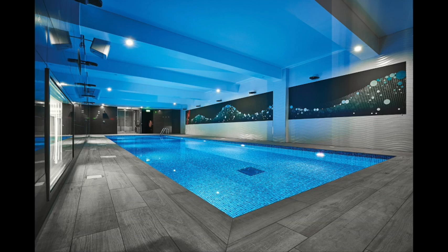Oh, that's interesting. What would you say is the most popular way to heat pool halls? Most pools are heated via ventilation systems. Typically, this would involve supplying air at a temperature of 45. So if it's off a boiler system with water at 80 degrees C or maybe even 70 degrees C, that would not be a problem at all because you'd have a difference of 80 degrees C water temperature to coming back at 45 degrees C, a 35 degree difference. If this was off a heat pump, the water was at 55, which is on the high side for most heat pump systems, then the difference would be 55 to 45, a 10 degree delta T.